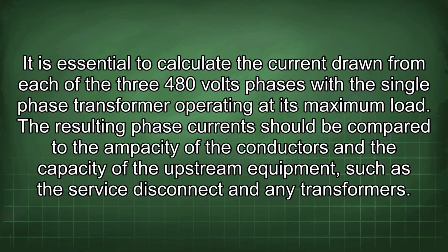It is essential to calculate the current drawn from each of the three 480-volt phases with the single-phase transformer operating at its maximum load. The resulting phase current should be compared to the ampacity of the conductors and the capacity of the upstream equipment, such as the service disconnect and any transformers.